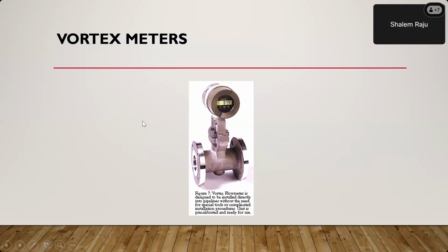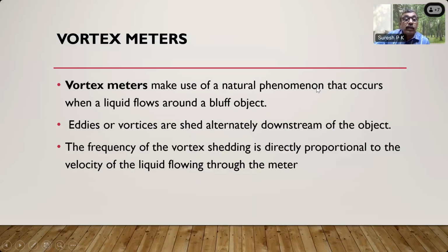Now, there is another meter called the vortex flow meter. Vortex meters make use of a natural phenomenon that occurs when a liquid flows around a bluff object. Eddies or vortices are shed alternately downstream of the object. So the frequency of vortex shedding is directly proportional to the velocity of the liquid flowing through the meter. That is the basic principle.